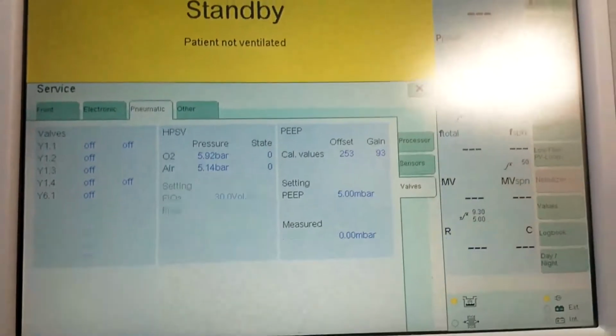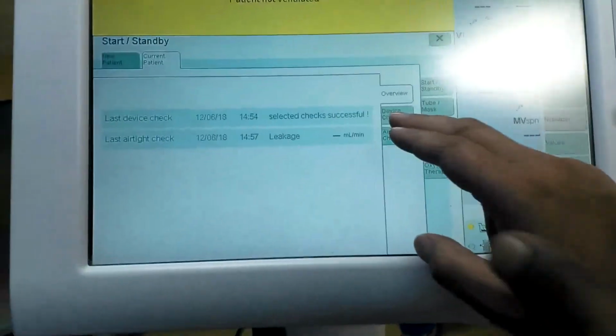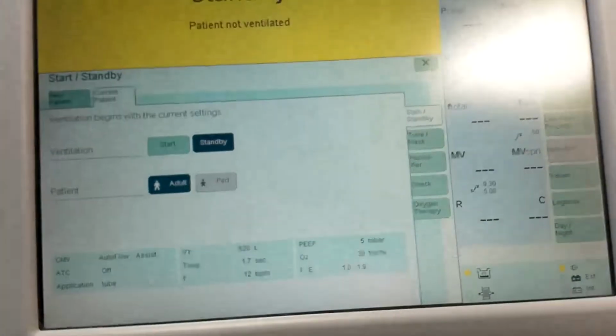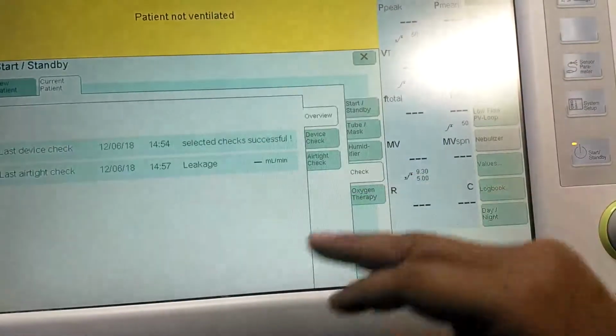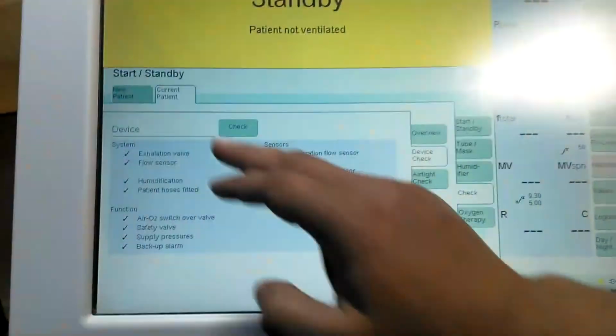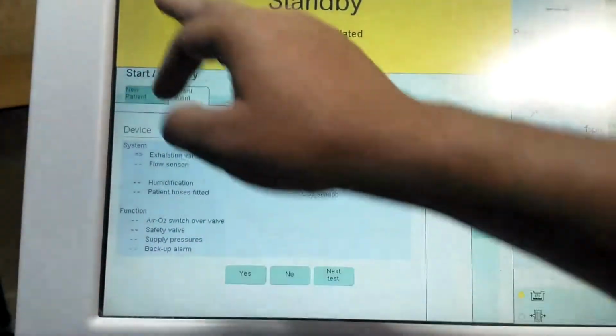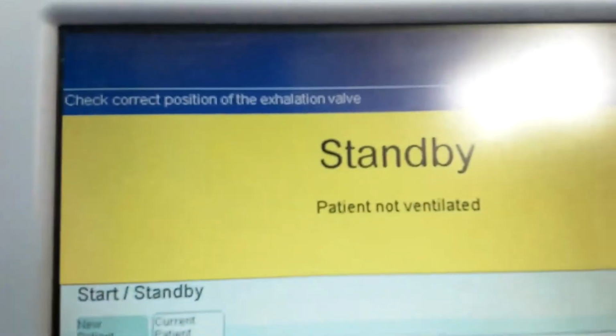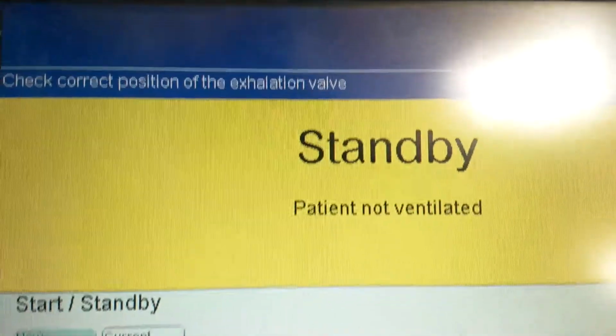Yeah, good. And now we will start the device check. Okay, start the check. Now we just need to follow the procedures. It says check correct position of the exhalation valve, and the white color part is the exhalation valve, and it is positioned properly and locked properly in the lock.